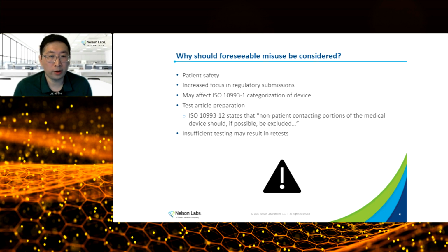When it comes to preparing a sample, Part 12 does state that any kind of non-patient contact component should be excluded from the testing. So this is very straightforward. However, this becomes an issue if something gets excluded, because as Katie said, you say, this isn't patient contact, there's no way it is, so we should just remove it. However, if the reviewer comes back and says, we don't agree with this approach, then you would have to retest it because it wasn't properly evaluated the first time around.